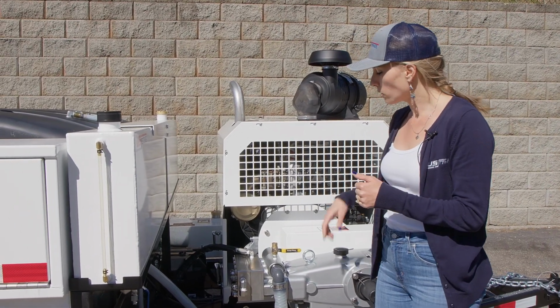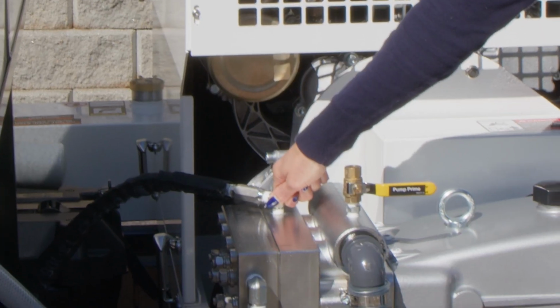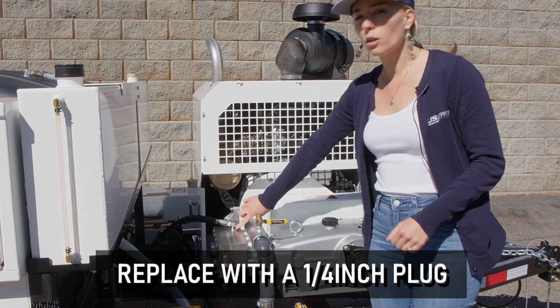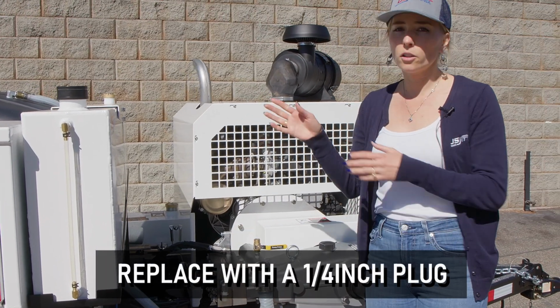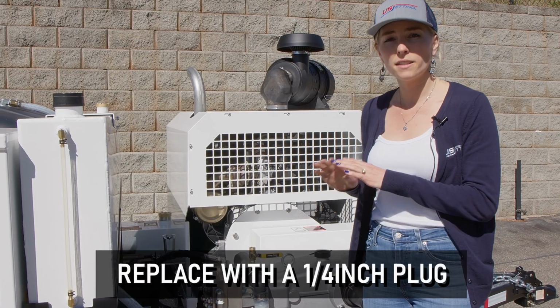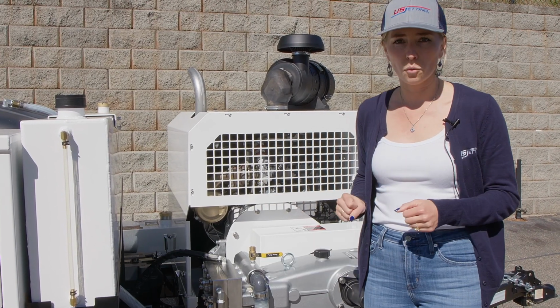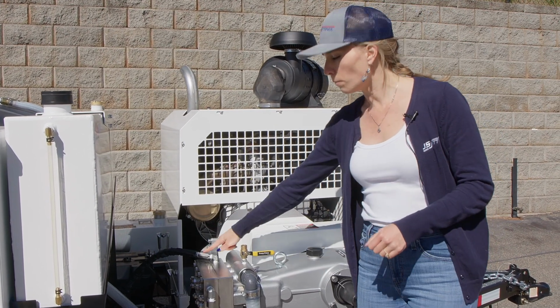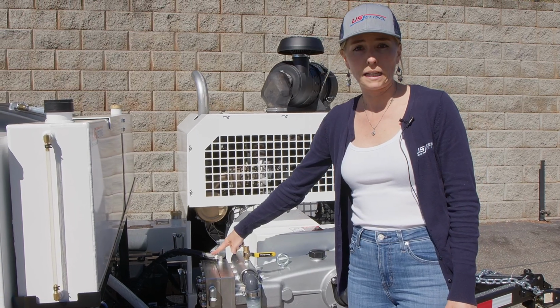You're going to remove this 90-degree fitting and replace it with a 1/4-inch plug, turn on the machine, turn on the water, and see if the pulsation goes away. If it goes away, it probably means the check valve is bad and needs to be replaced.